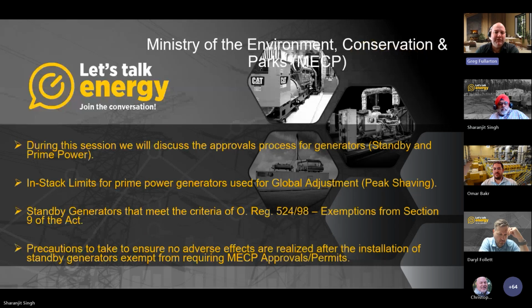Great, thank you very much. Okay, just before I get started, I want to say that most generators today meet the Tier 1 emission criteria for diesel. Most new natural gas generators meet the 9.2 grams per kilowatt hour NOx in-stack limits for standby generators, and most of them meet 75 decibels at 7 meters.